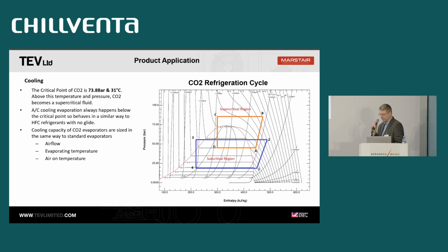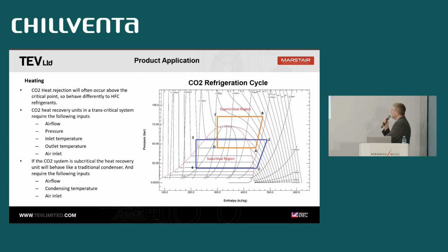On the heating side, it's more complicated, though, because there are two systems that you may get, because you're now in the supercritical region. If you're transcritical, you need a lot more information. As well as the airflow and the inlet temperature that we needed on the cooling side, we also need the pressure of the refrigerant, because that's the amount of refrigerant in the pipes relative to the pressure. We also have the inlet temperature and the outlet temperature of the gas. In heat exchange, it's generally the temperature difference between the air and the temperature of the fluid within the heat exchanger that's important. So you have more parameters and more variables involved in the transcritical region.